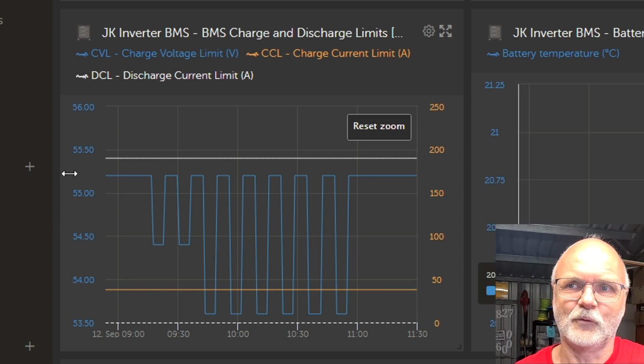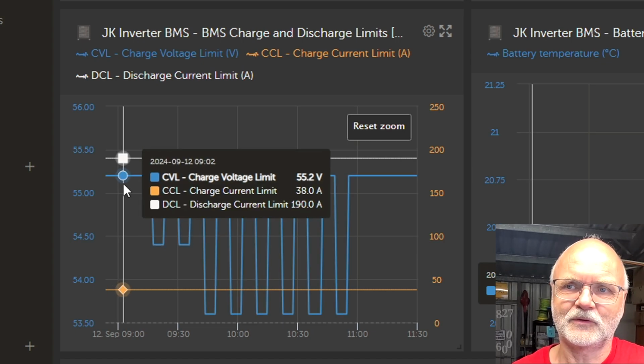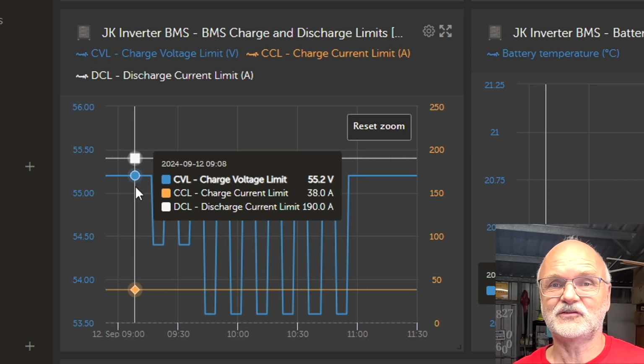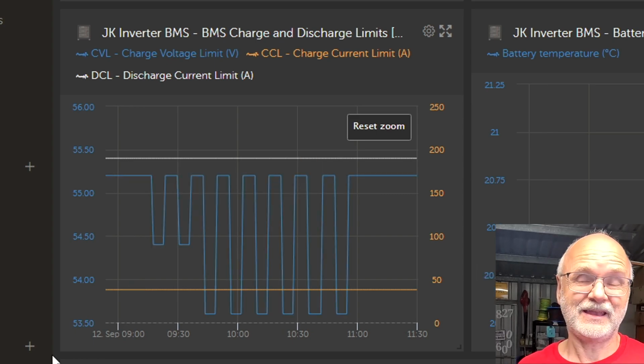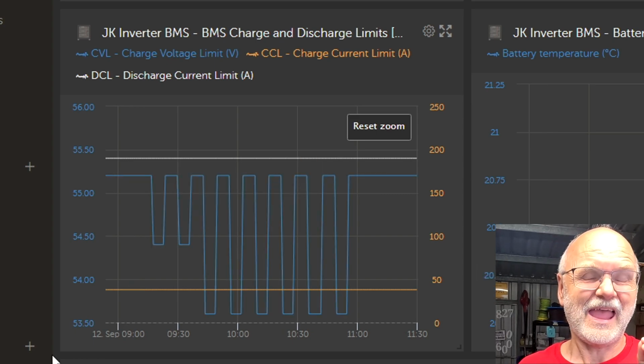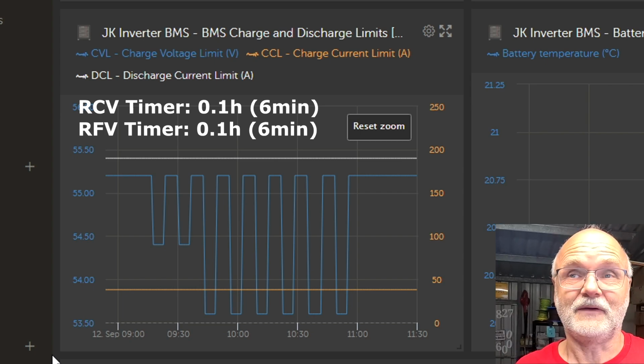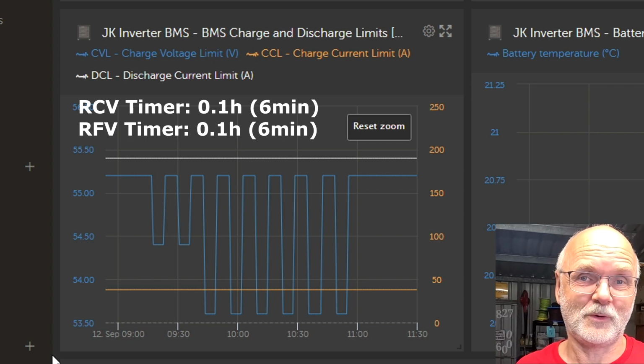This is the charge voltage limit. At the beginning here it was 55.2, and then I installed the new firmware. I've set the RCV timer as well as the RFV timer, both set to 0.1 hours just for the purpose of testing here.